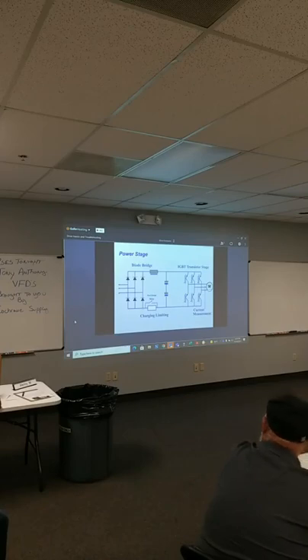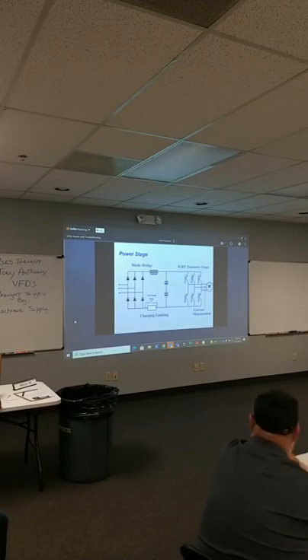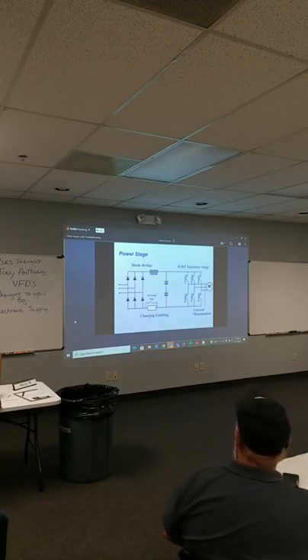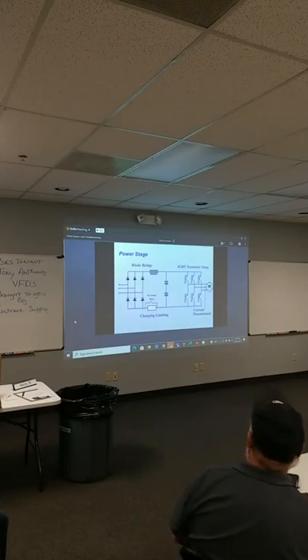So take your ohm meter, put it on L1 and on the plus side of your DC bus. And then you reverse it, your black and red leads. In one direction you'll see a short, in the other direction you should see an open. If you see an open in both directions, you've got a bad diode, and you know you've got a problem with your diode bridge. So the real simple way: you do that for L1, L2, and L3 to the plus side of the bus, and you also do it to the minus side of the bus.